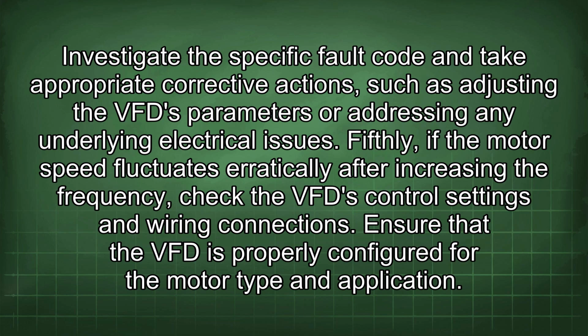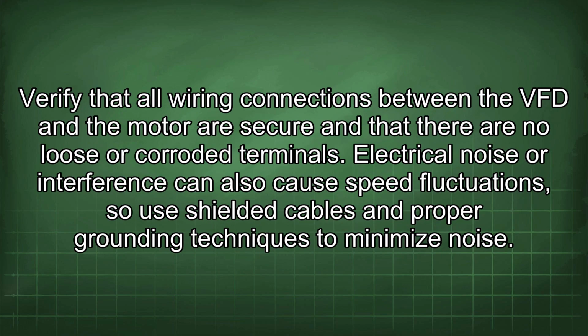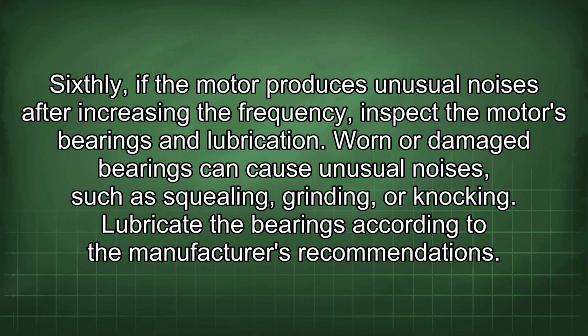Fifthly, if the motor speed fluctuates erratically after increasing the frequency, check the VFD control settings and wiring connections. Ensure that the VFD is properly configured for the motor type and application. Verify that all wiring connections between the VFD and the motor are secure and that there are no loose or corroded terminals. Electrical noise or interference can also cause speed fluctuations, so use shielded cables and proper grounding techniques to minimize noise.